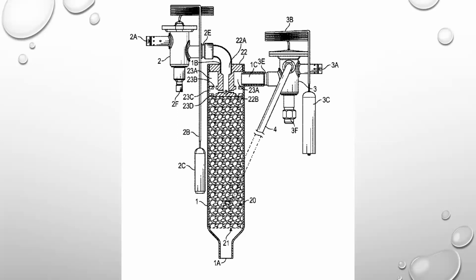The chamber itself is patented. The fill inside there is a specialized fill, but the very top is really what makes this thing work. It's an atomizing chamber at the top. And at the top, the hot gas comes in, preheats the tube, and then as the liquid comes in to de-superheat, that liquid's flashed up there, and that chamber ensures that only cool gas gets back to the compressor. It's been tested and designed many different ways.